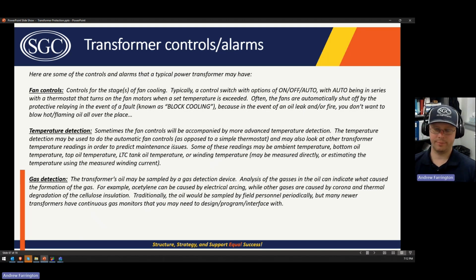Temperature detection, controlling the fans, providing warnings for maintenance issues. Gas detection, not to be confused with the nitrogen blanket that may be on the top of the mineral oil if you don't have a conservator tank, keeping that positive pressure that keeps the air out. It's not that kind of gas detection. There are actually trace gases that can exist in the mineral oil itself.